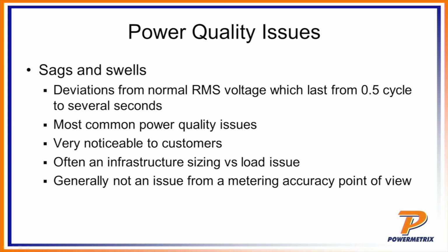The cause of a sag or swell is typically due to infrastructure sizing and a load issue. Transformers are unregulated to some degree, and so as you switch in large loads, that will cause a sag or swell. If another load comes off, basically removing that load will cause the voltage to jump up. So it really depends on the load being applied to the system.